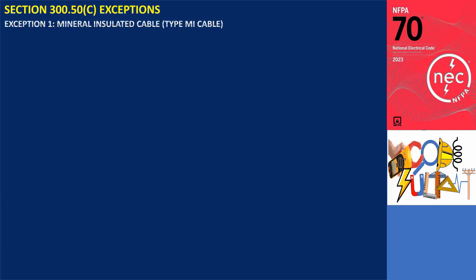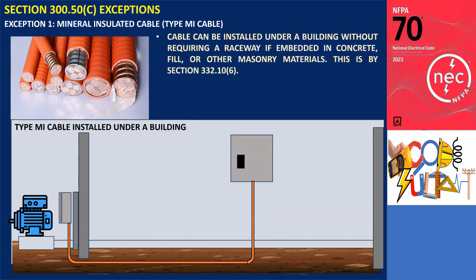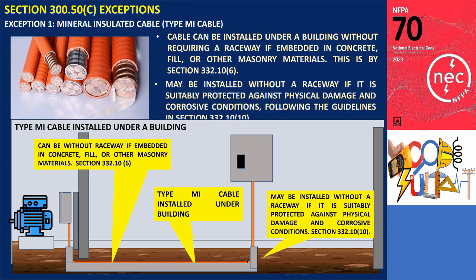Section 300.50(C) Exceptions. Exception No. 1: Type MI Cable. Type MI Cable can be installed under a building without a raceway if embedded in concrete, fill, or other masonry, as outlined in Section 332.10(6). It is also permitted for underground installations, provided it is adequately protected against physical damage and corrosive conditions, following Section 332.10. This flexibility makes Type MI Cable suitable for applications where raceways are impractical.